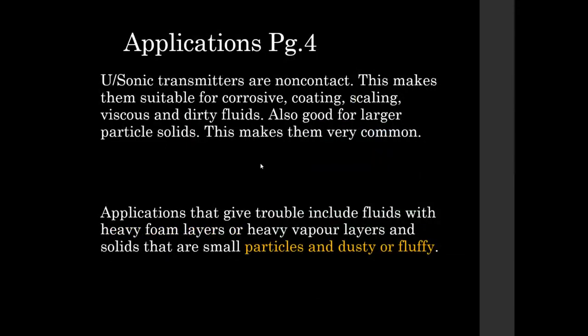Applications. Ultrasonic transmitters are non-contact devices, which makes them excellent devices for applications which involve corrosive coating, scaling, viscous fluids, dirty fluids, and larger particles, solids. As a result of their suitability for all these different applications, they are very common. They do, of course, have issues, and as we go through the ILMs here, probably the biggest thing to focus on is the strengths and weaknesses of the different technologies and variations of the devices as we look at them.